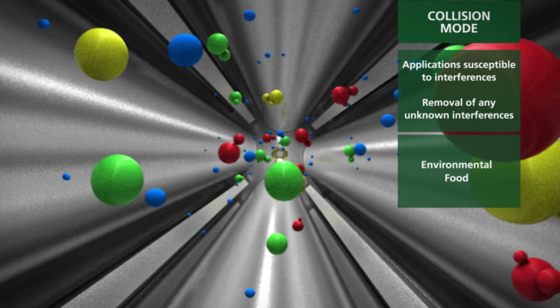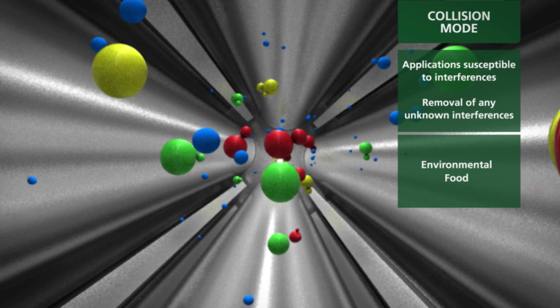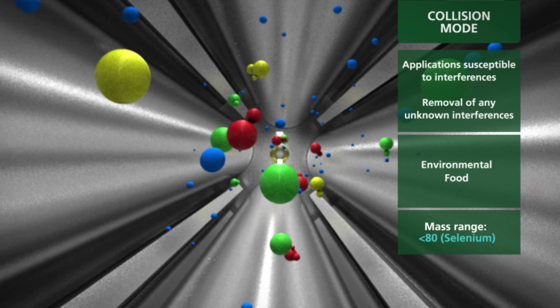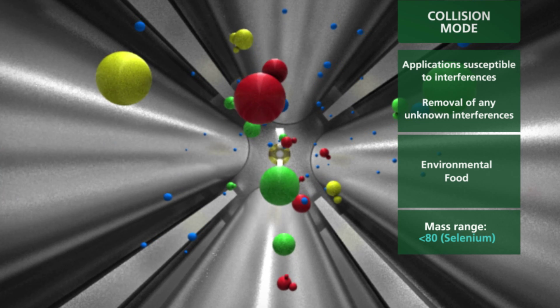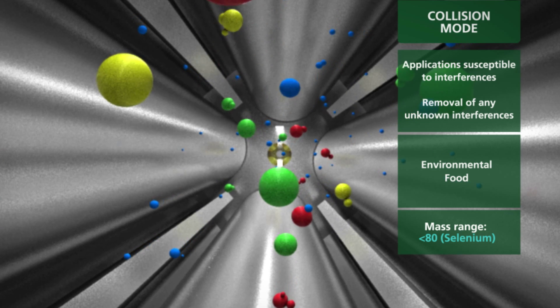Like other collision cells, Nexion's collision mode works very well with analytes below mass 80, selenium, and provides a good balance between interference removal and instrument performance.